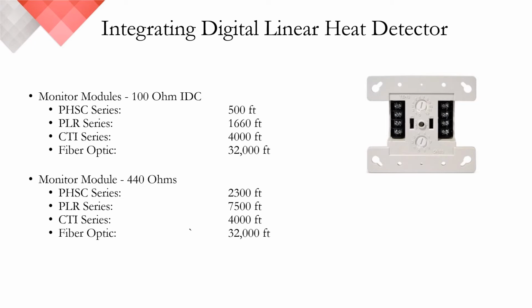This slide provides a good illustration of exactly how much these IDCs can directly impact the zone coverage capabilities. In this example, we show two different addressable modules, the first with output values of 100 ohms and the second at 440 ohms. By dividing the IDC's output value by the resistance value of the detector, we get some surprising numbers. With the 100 ohm IDC, our calculations show we're able to support up to 500 linear feet of PHSC and almost 1,700 feet of PLR. We see similar limits in the 440 ohm IDC, but our lengths are longer due to the electrical properties of the module.